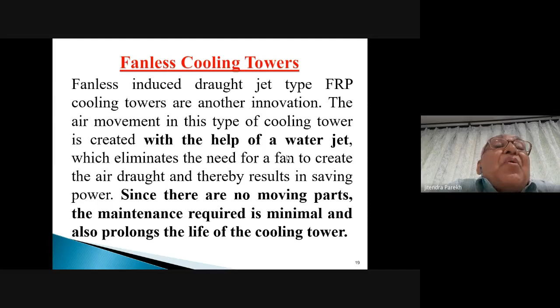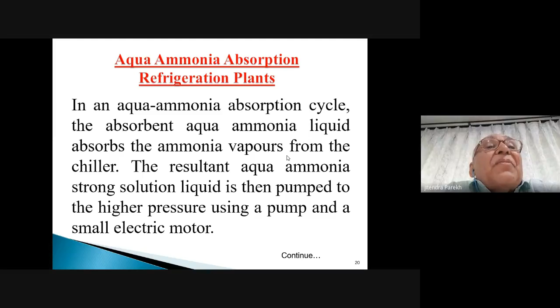Now, aqua ammonia refrigeration systems, which are absorption type cycles. The absorbent is aqua ammonia liquid, which absorbs the ammonia vapors from the chiller. The resultant aqua ammonia strong solution liquid is then pumped to a higher pressure using a pump and a smaller electrical motor. So when you use this aqua ammonia system, your power consumption goes down substantially. Next, please.